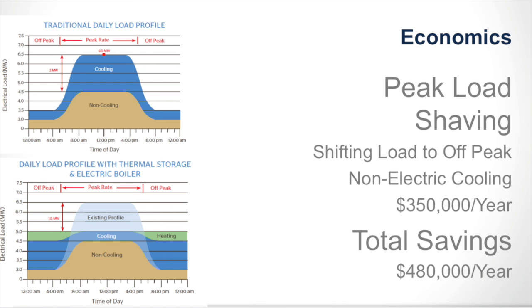So what we do with a chilled water storage tank is that we shift this load to here. So what does that mean? It means I only need half the tonnage capacity. Let's say, the example we used today in some classes was, let's say this is 1,000 tons, and if I do this, my peak load is now only 500 tons from the chillers because I'm going to put it in storage and then pull the other 500 tons out of storage. So I have to buy less equipment, less stuff to run, less stuff to maintain.